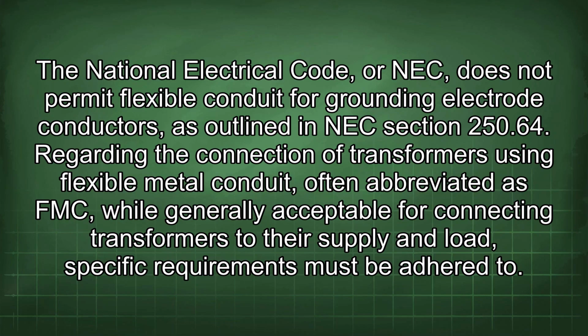The National Electrical Code, or NEC, does not permit flexible conduit for grounding electrode conductors as outlined in NEC section 250.64. Regarding the connection of transformers using flexible metal conduit, often abbreviated as FMC, while generally acceptable for connecting transformers to their supply and load, specific requirements must be adhered to.